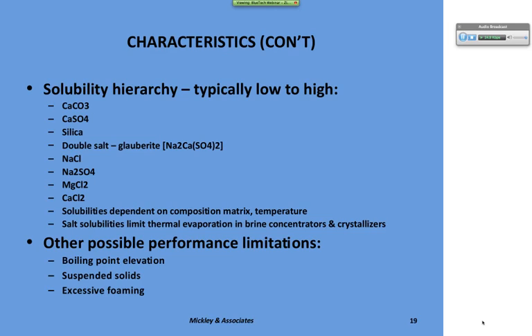Many times the double salt glauberite, which is a sodium calcium sulfate salt, is the limiting aspect or limits the performance of thermal equipment. If it doesn't limit performance, many times the limitation is due to sodium chloride or sodium sulfate or some other salts.